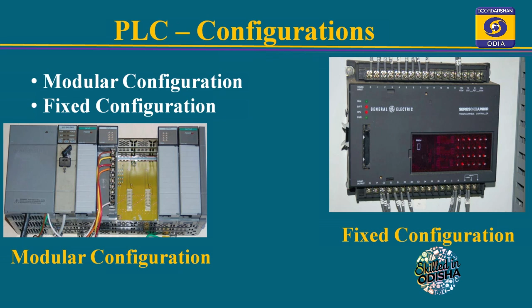So PLCs are available in two configurations. One is modular configuration, another is fixed configuration. The modular configuration has the advantage over the fixed configuration that it can be provided with extra IO module facility, meaning more input output modules can be added to the modular configuration.